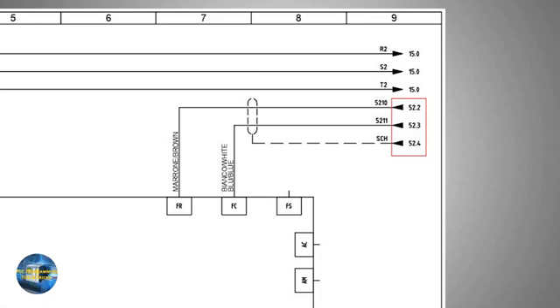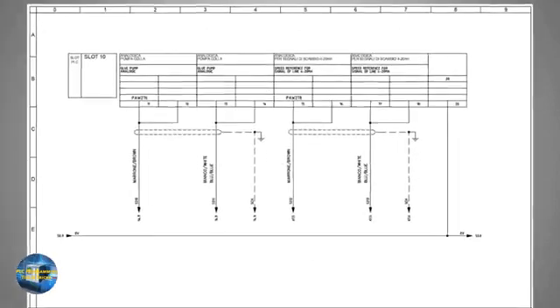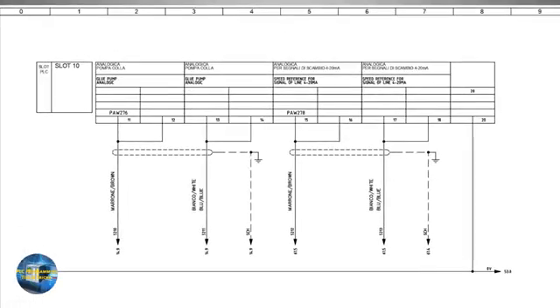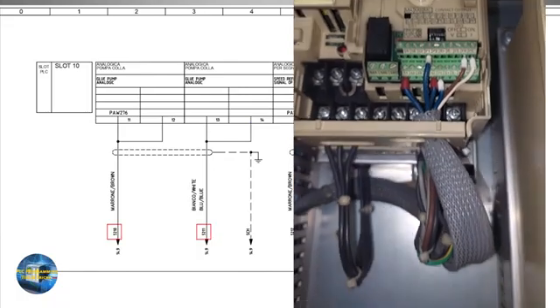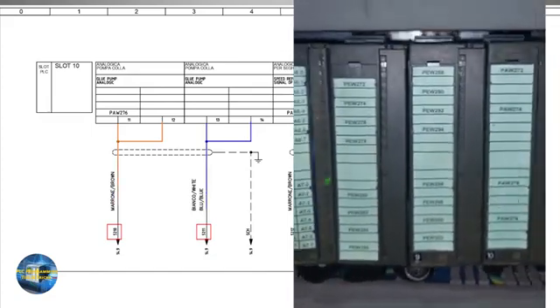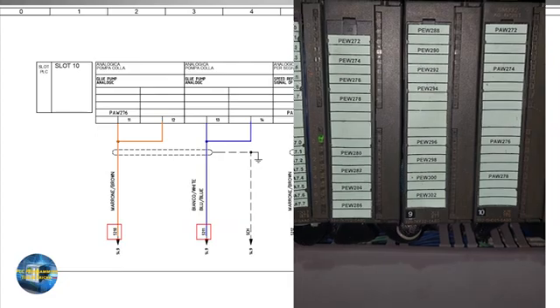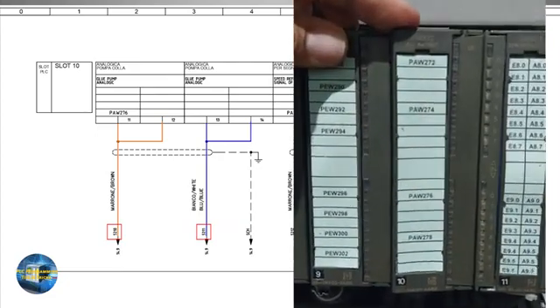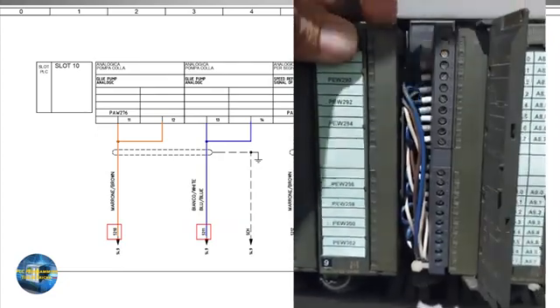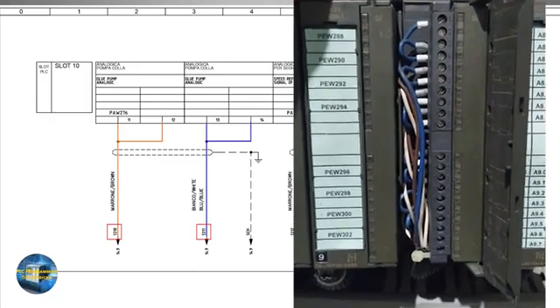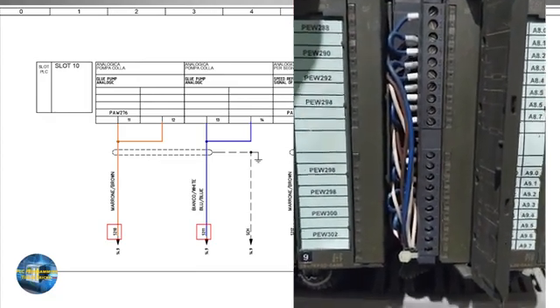What does this mean? This means that these wires are coming from sheet number 52. So we will go to sheet number 52, and here you can see that the wires S210 and S211 are connected to the analog output of the PLC. The brown wire S210 is connected at terminals 11 and 12 and the blue wire is connected at terminals 13 and 14.